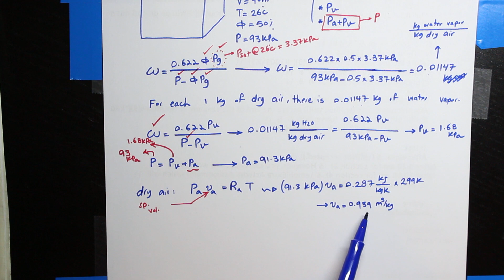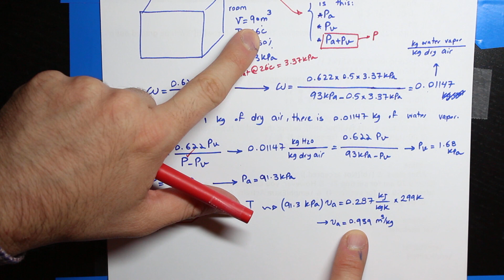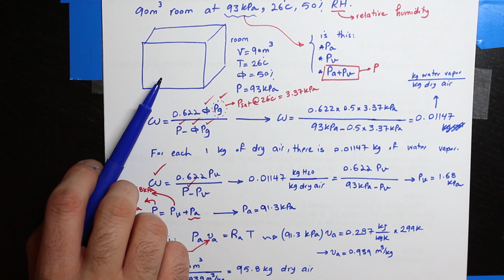Now, because we have the volume of the room, and that volume is equal to 90 meter cube, I'm going to utilize these two numbers to find the mass of air. So M dry air is, let's say, volume divided by this: 90 meter cube divided by 0.939 meter cube per kilogram. If you are wondering why this ratio gives me the mass, just look at the unit. Here I have meter cube, here I have meter cube per kilogram. So this meter cube cancels this meter cube, and the kilogram goes on top. So M is going to be 95.8 kilogram dry air. So in this room, the mass of dry air that we have is 95.8 kilogram.